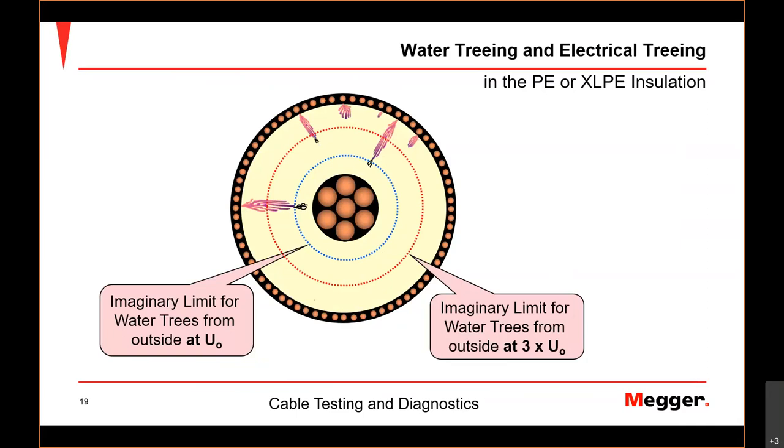And you could stop the test and say, okay, I can operate this now for a few more weeks, but we have to fix this quickly, knowing that our test has already damaged the cable further, right? Has been growing the electric tree. But we saw that early, so we could stop. Okay, most people would probably say, you know what, let's just finish that hour. We know where it is, we have the pre-location, we are right here in the middle of the week, so we can easily fix it, it's out of service anyway, and then we're fine. That's good. And actually, you would even see if there are 2 or 3 points, because you would see them as separate spots, so another advantage that I've never really thought about, but yeah, good.